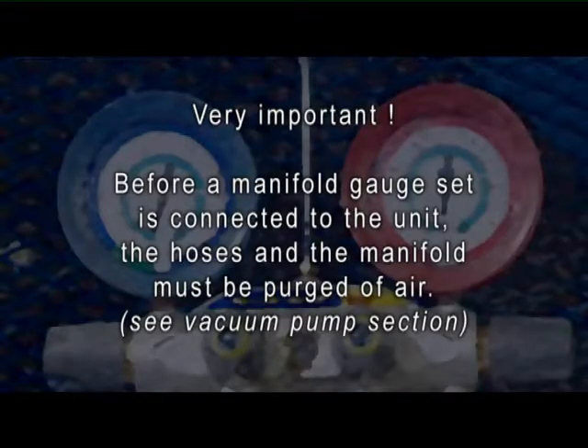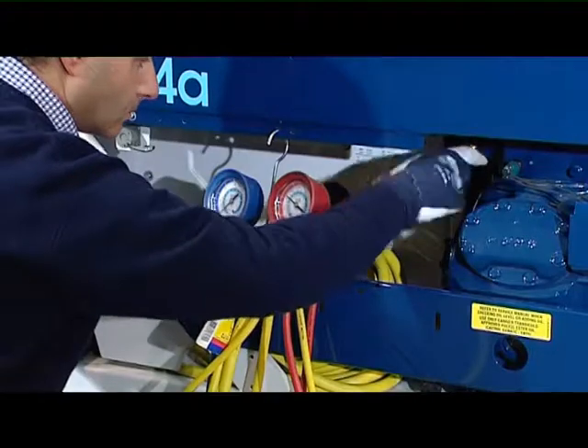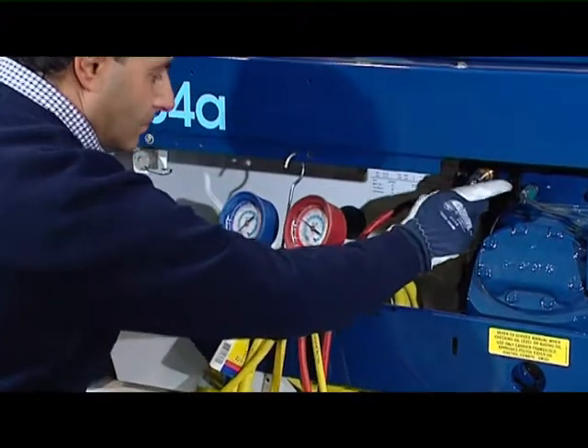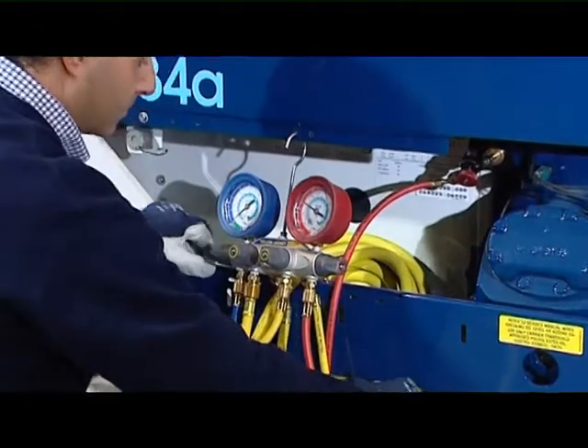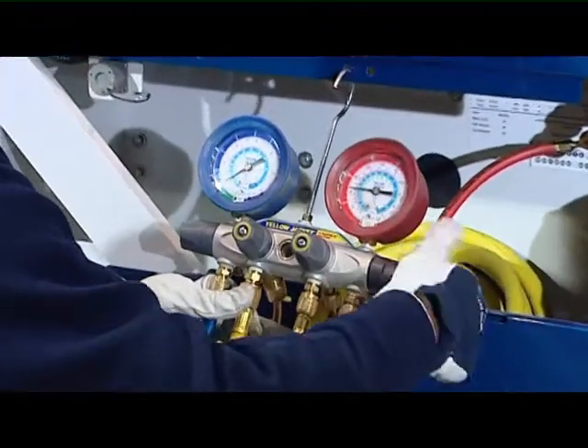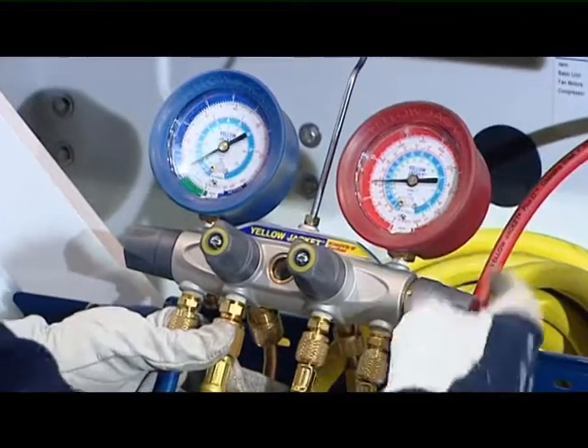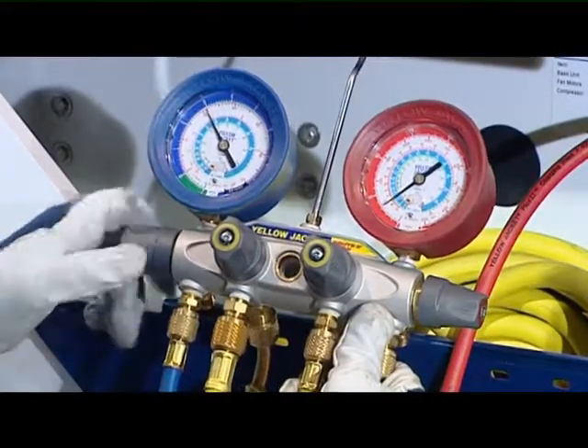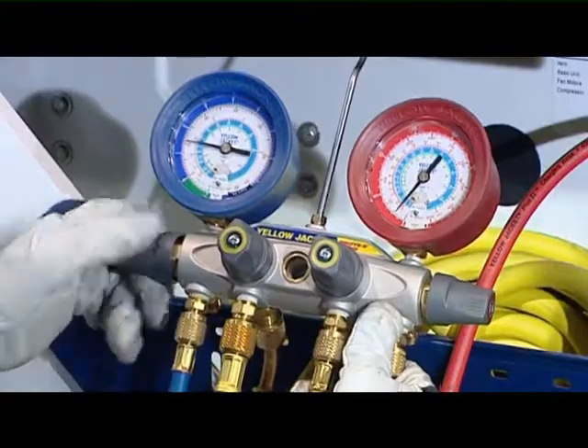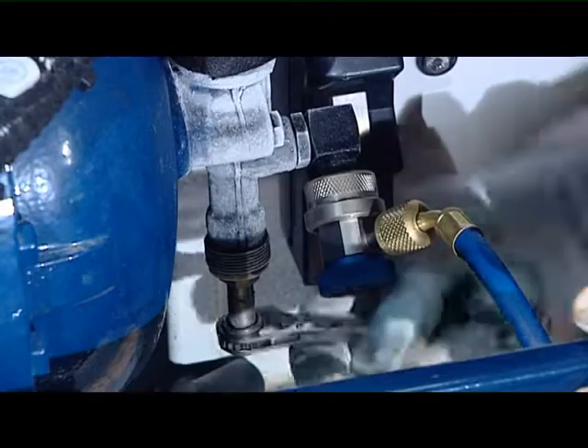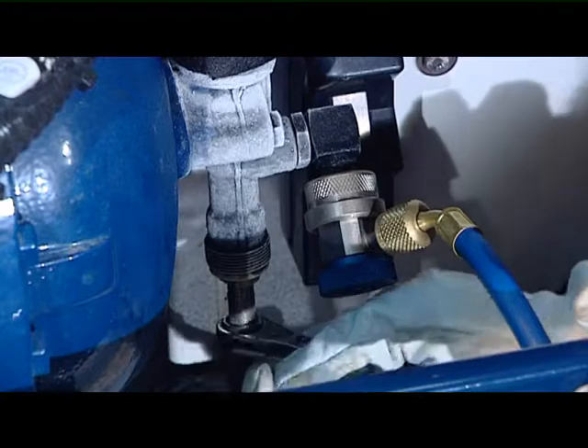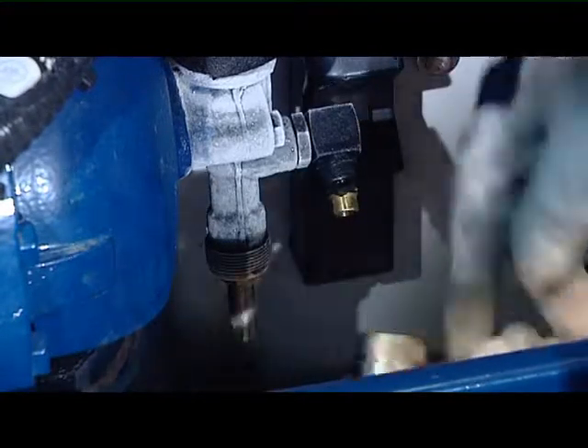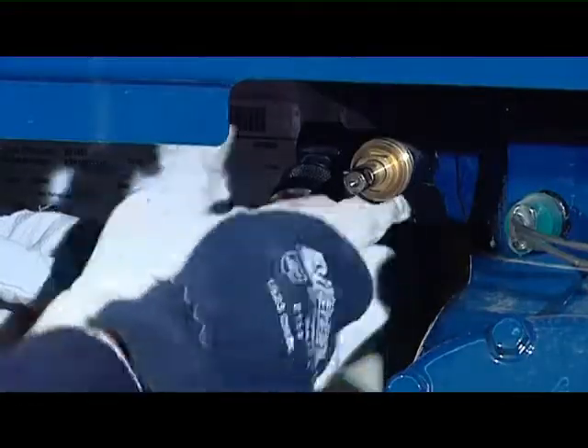Very important. Before a manifold gauge set is connected to the unit, the hoses and the manifold must be purged of air. See vacuum pump section. To properly remove a manifold gauge set, first backseat the compressor discharge service valve, then open both valves on the manifold. In this way, with the compressor running, the refrigerant inside the manifold will be aspirated into the compressor. Backseat the compressor suction service valve and disconnect the manifold hoses from the unit.